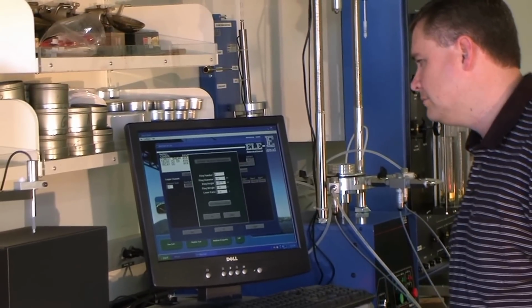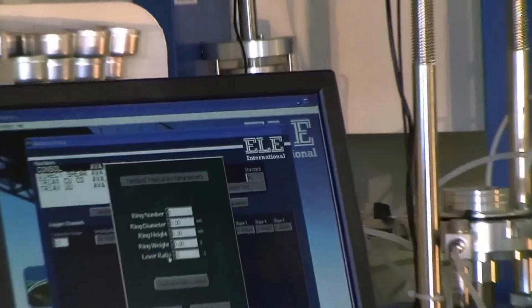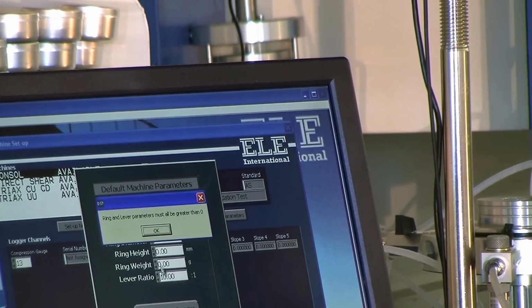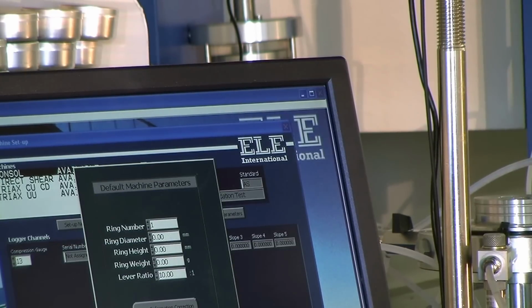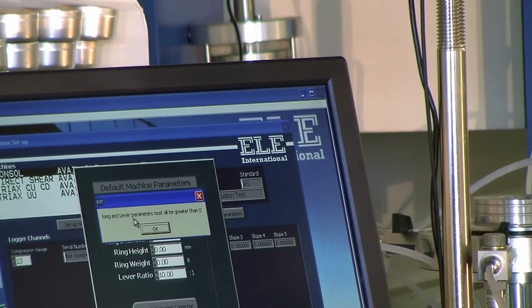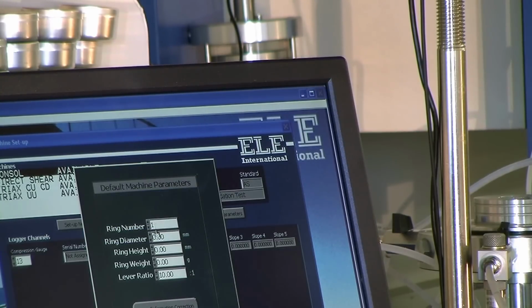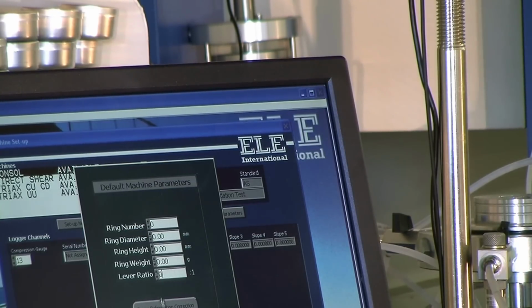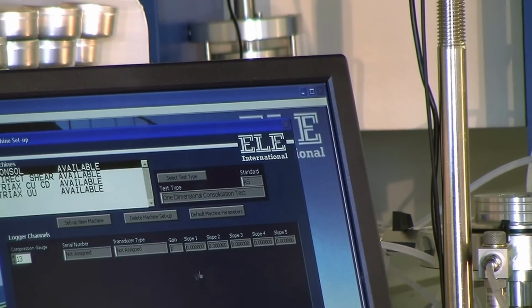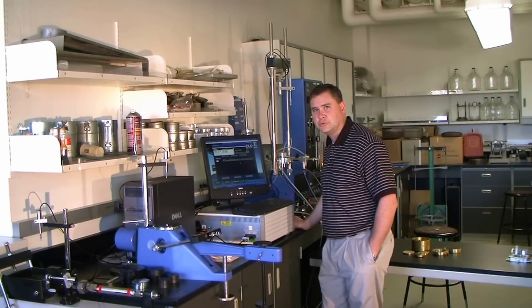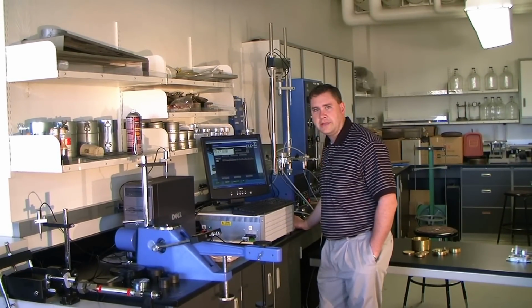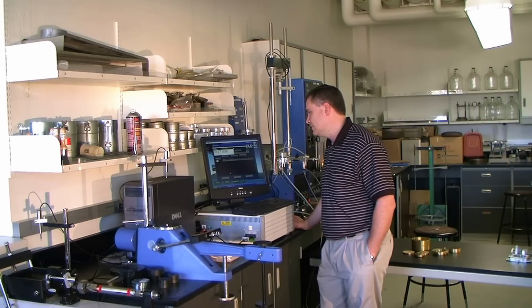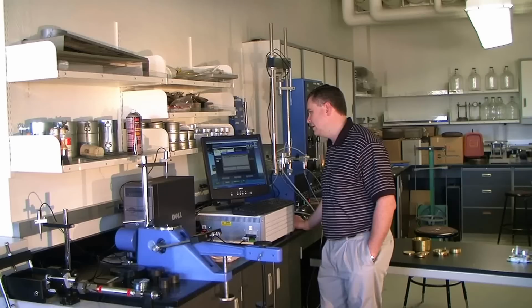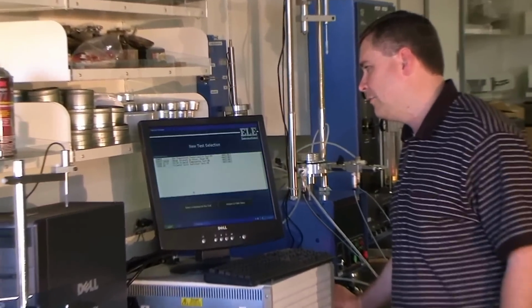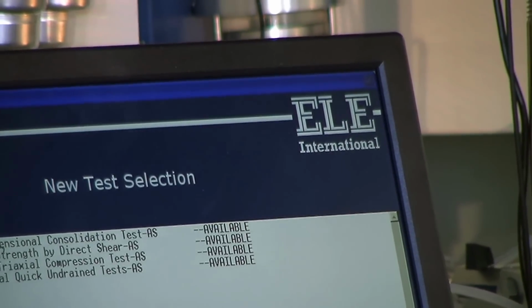We can put this as ring 1, lever weight ratio 10 for now, and hit OK. It's telling me the ring and the lever parameters must be greater than 0. So let's go ahead and just leave them at 0 now. We'll fill them in as we test each time. But if you know you're going to test each one the same way, you can certainly input those as the default values. Then hit apply, and that brings in the calibration information, and hit OK, and it asks you if you want to save it, say yes. And now when we click new test, we have a consolidation machine on there as well.